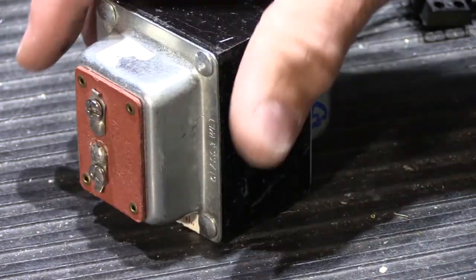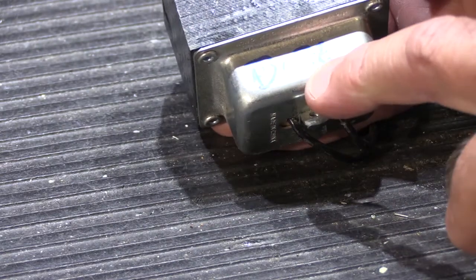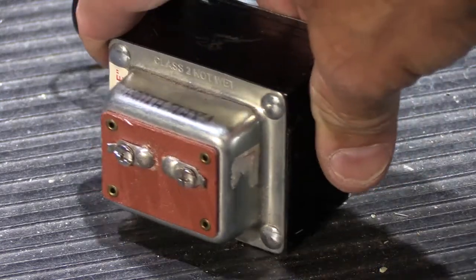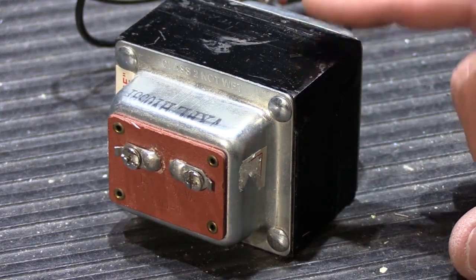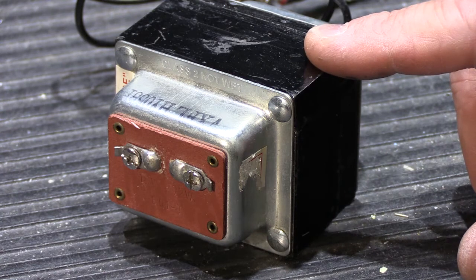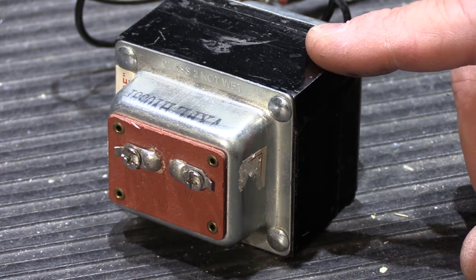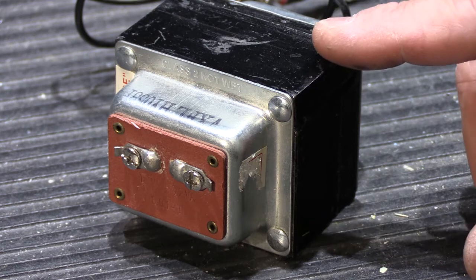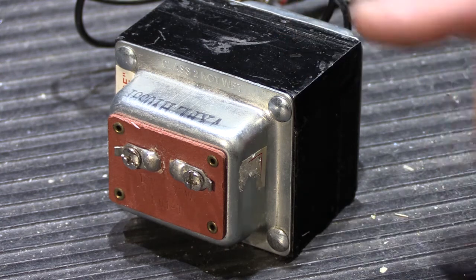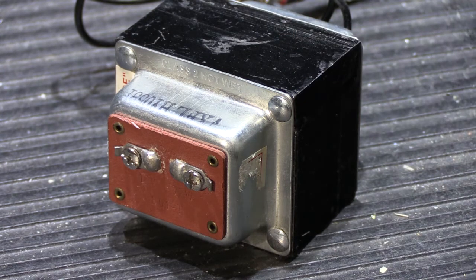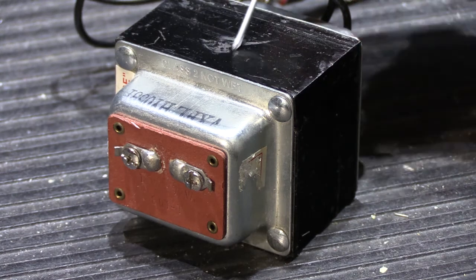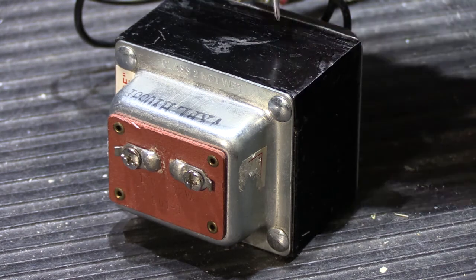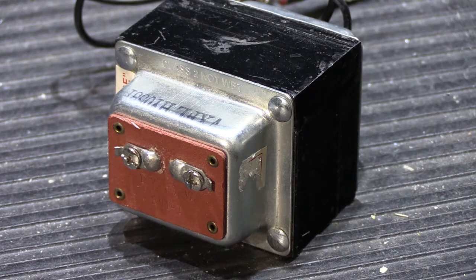This 801T is marked in a special way - it says down here, buzz. This 801T actually came out of one of my customers' homes locally, and the complaint was that it buzzes, and it buzzes a lot - well, at least in her house it buzzed a lot. A buzzing transformer is caused by problems with the laminations in the core, where some of them most likely separated or weren't squeezed together properly in the first place, creating a transformer that buzzes.